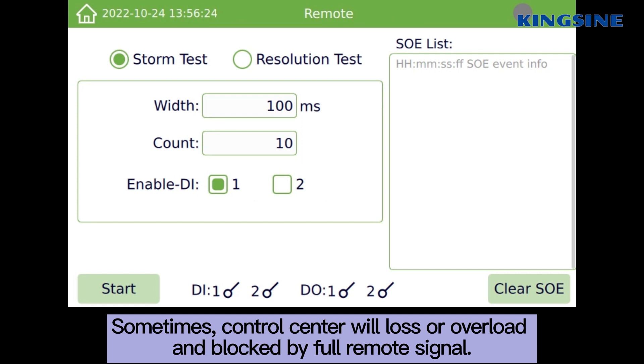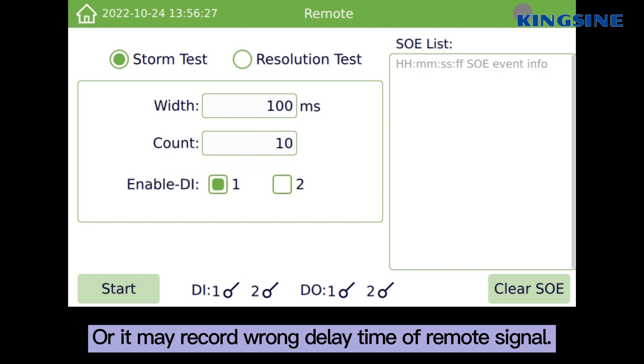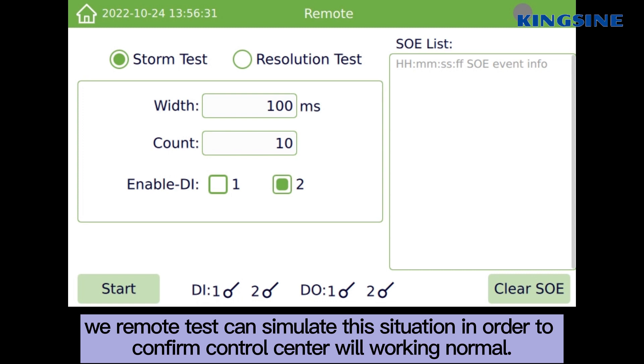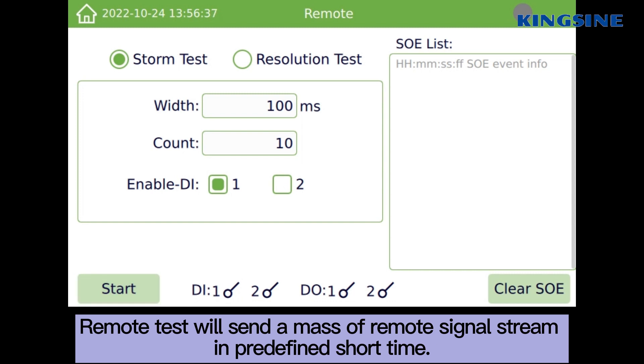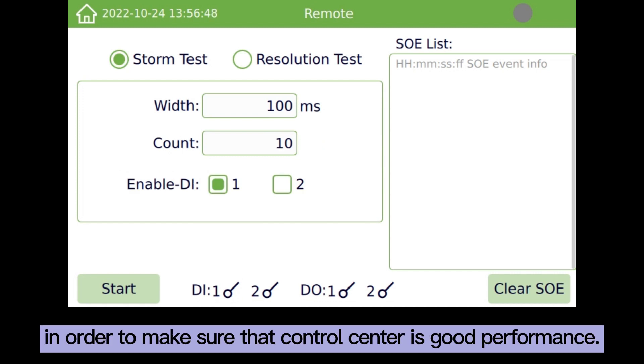Sometimes a control center will lose or overload and be blocked by a full remote signal, or it may record the wrong delay time of a remote signal. The remote test can simulate this situation in order to confirm the control center will work normally. The remote test will send a large number of remote signal streams in a predefined short time. In this case, we can check the delay time between the control center and the software setting, and define the interval time of each remote signal to ensure the control center is performing well.